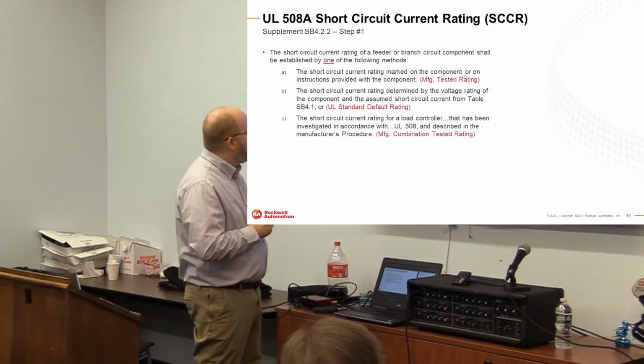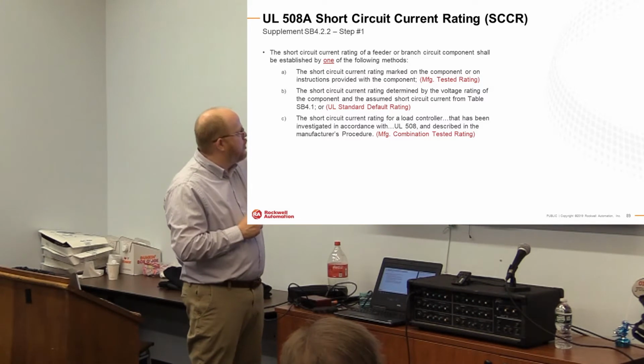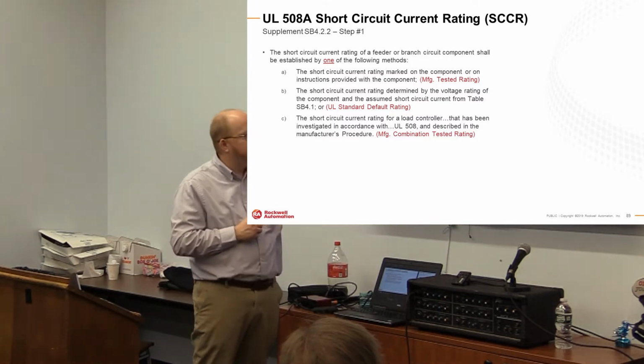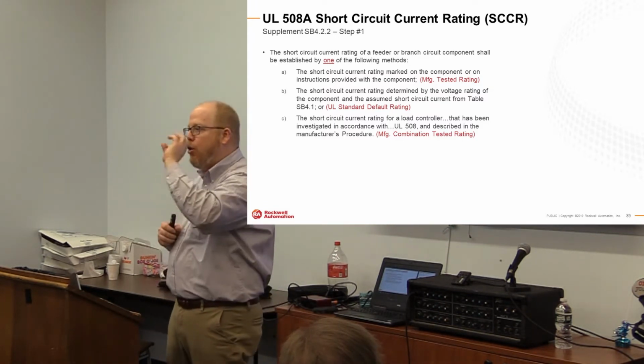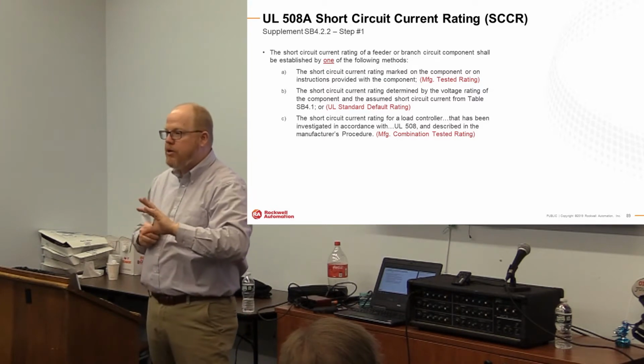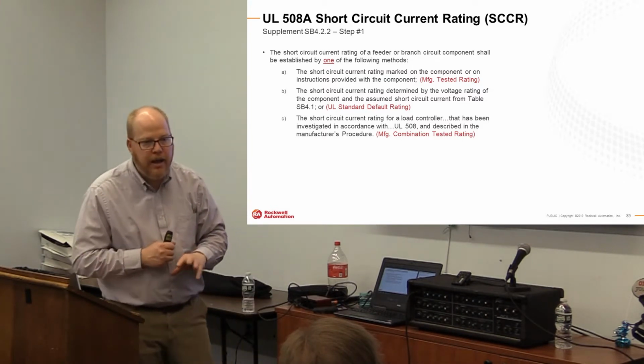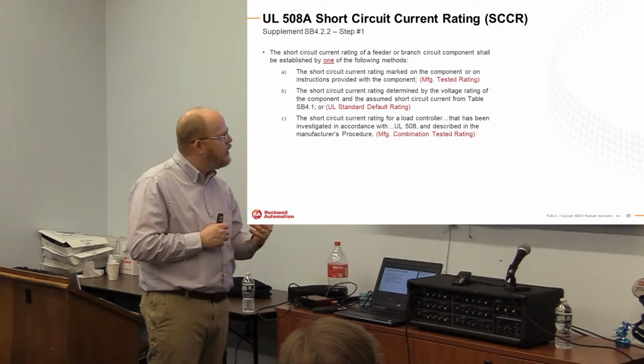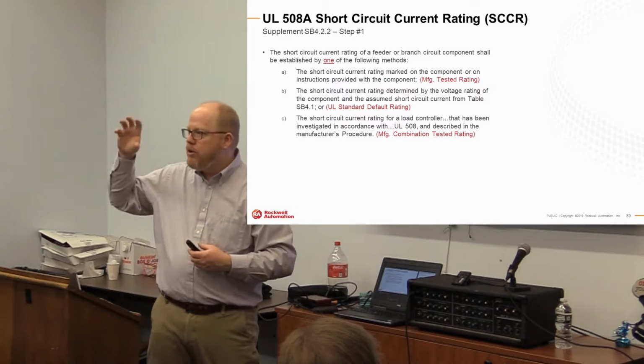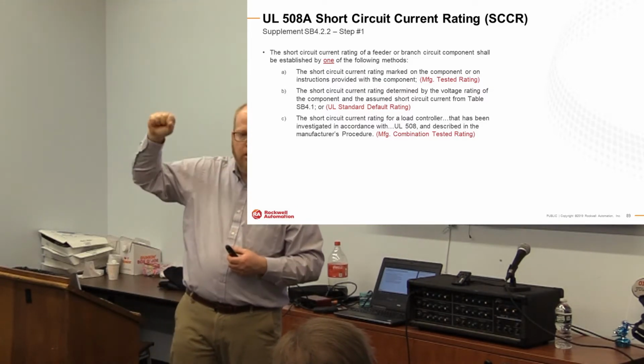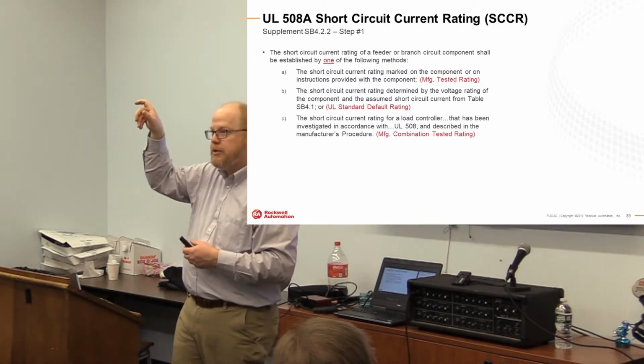So this would be, for example, the first one: the short circuit current rating marked on the component. So this would be a breaker, an overload, a contactor. They have a rating marked on it, and it's usually a manufacturer test rating. So on the side of our contactor, you will see what our short circuit current rating for that component is.